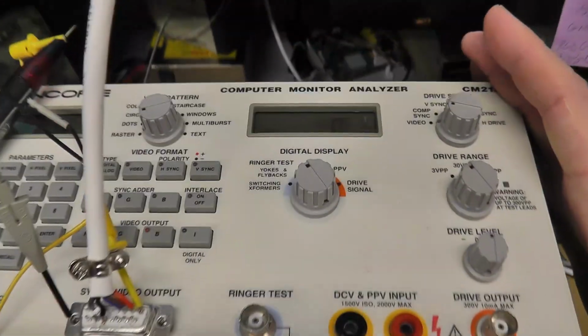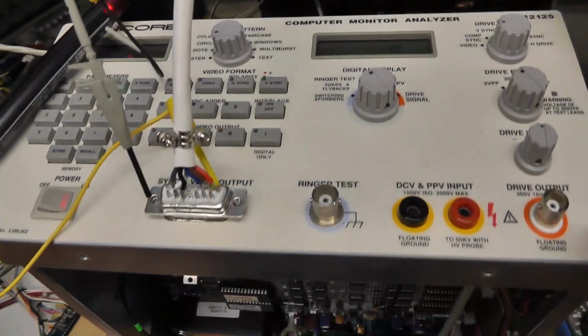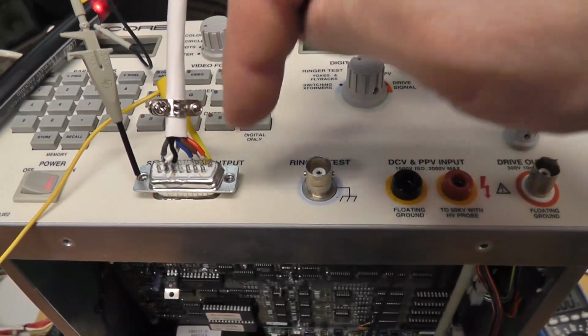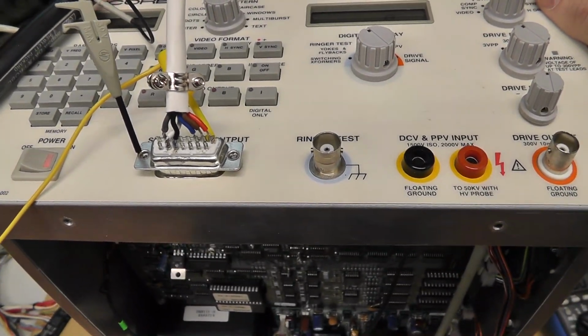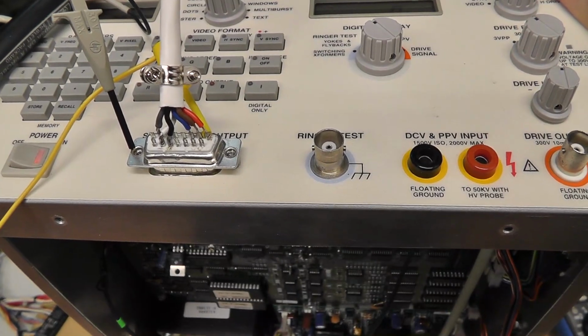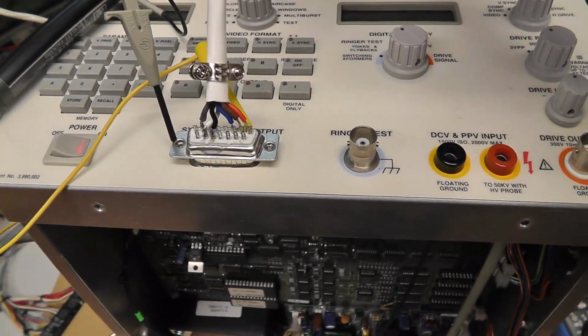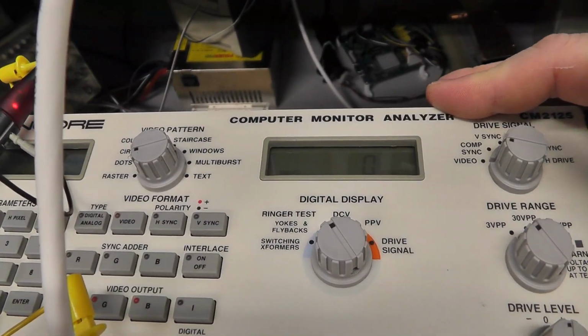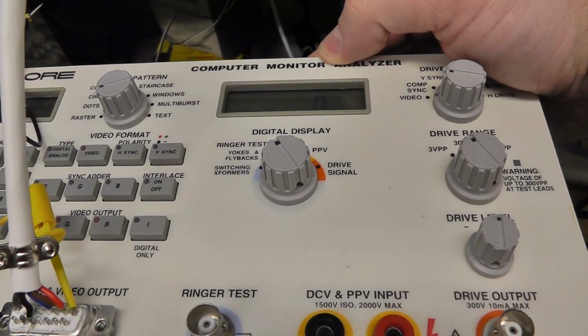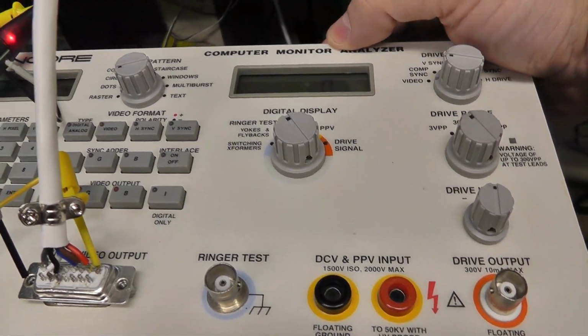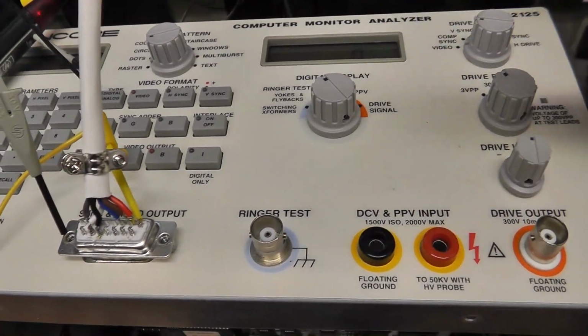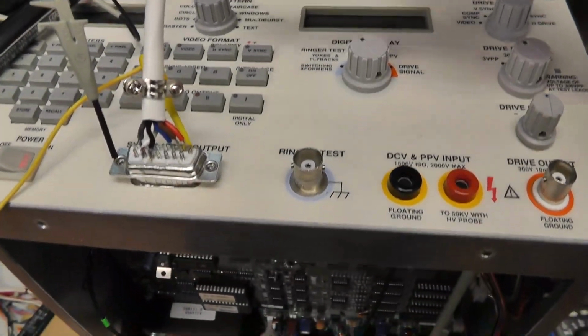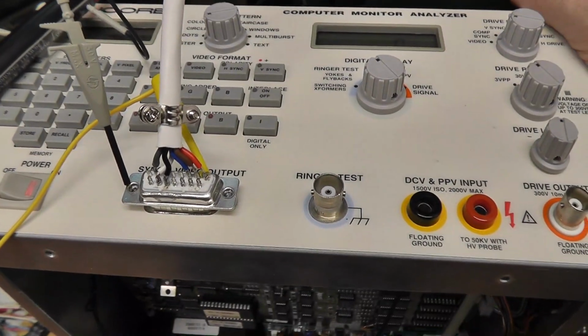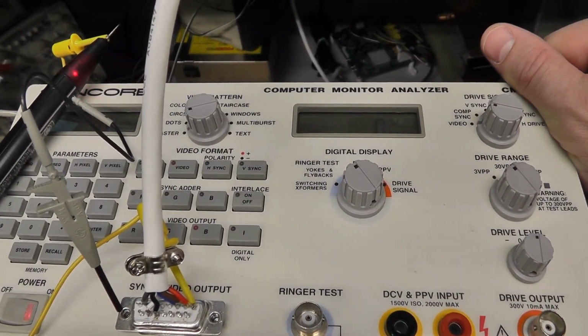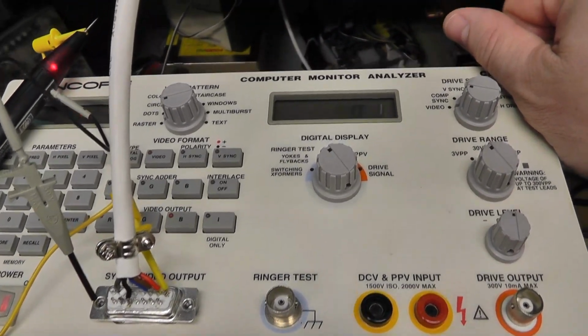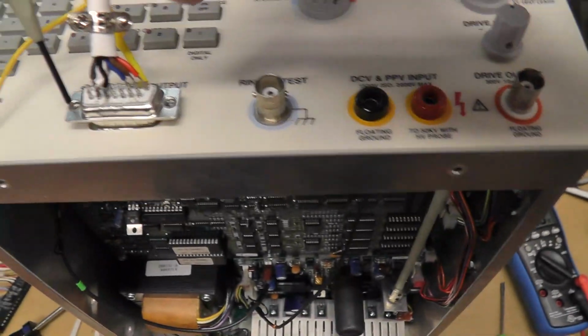Somebody had reported that when they were using this Sencore computer monitor analyzer to test arcade monitors, the image was dim, and it's probably because the input signal is not 4 volts peak to peak like what's coming off an arcade PCB. This is typically testing a computer monitor, where the VGA standard I think is 0.7 volts peak to peak. So using this for arcade monitors might not work that well, but there also is an amplifier you can buy. There's a couple example circuits for VGA to RGB arcade monitor amplifiers that boost it from like 0.7 volts to 4 volts.